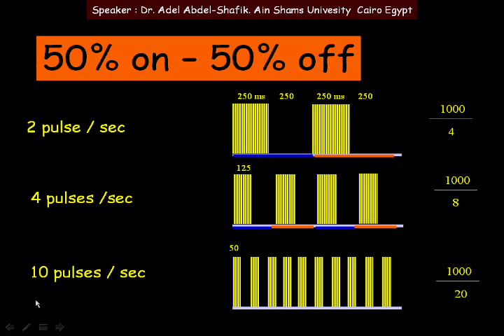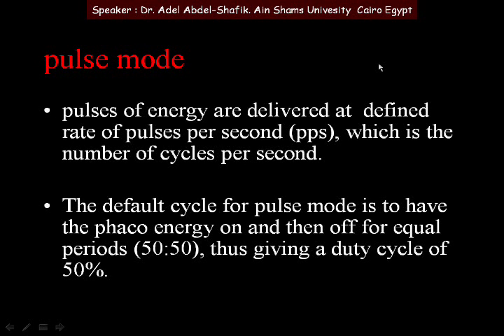Regardless of the number of pulses, in the whole second 50% of the time is on and 50% is off — it doesn't matter how many pulses are set. The pulse mode delivers pulses of energy at a definite rate of pulses per second. The default duty cycle for pulse mode is 50% on and 50% off.